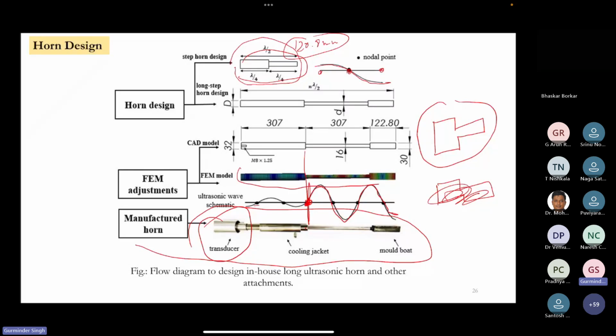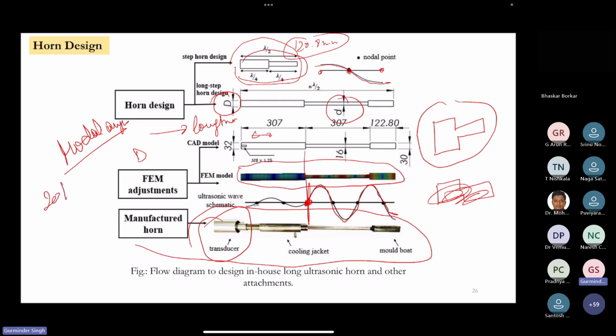So you have to do a lot of FEM around this. You have to do modal analysis, which gives you the vibration frequency in the longitudinal direction. It is really important because you have to take care of the left-hand side diameter D and the small diameter d, and also the length. It should have the same frequency of 20 kilohertz as your transducer frequency to have resonance, so that you can transfer the vibration from one end to the other. Also, it should have a longitudinal mode shape, so that the vibration goes in only one direction. It should not reflect to another direction.